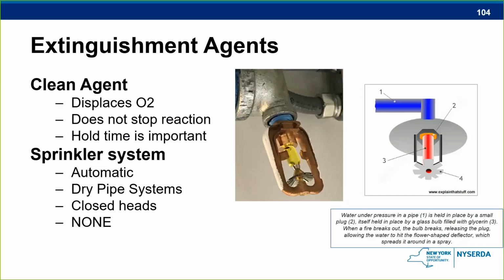In New York City, we're concerned about these things being used to put fires out in these energy storage systems. Because if you have an internal short circuit, once you remove that clean agent, that internal short circuit will continue to go, and it may cause the fire to go. So when people put these things in there for lithium-ion or other types of chemistries, they should prove that the clean agent will work to put that fire out.